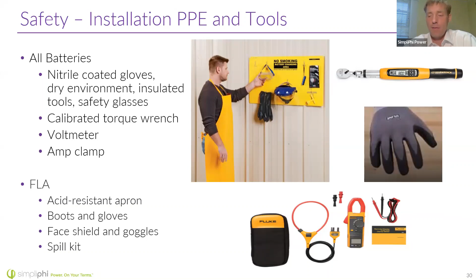When you're installing our batteries, remember to have the breakers off. All of our batteries have breakers, for your safety and the safety of the system. Turn all the batteries off, make your connections. If you don't know the proper way to make those connections, we have resources and trainings for installations. Always be careful not to short the terminals, as I just told you a story about that happening.